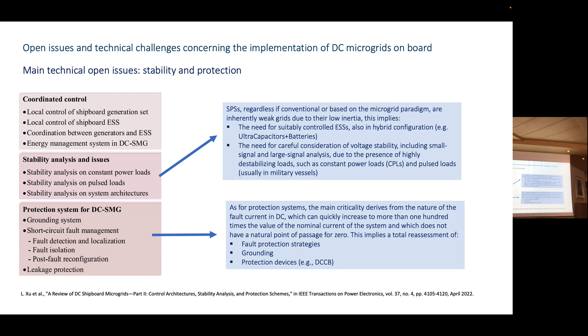So the consolidated protection systems used for AC systems are not appropriate, and the protection system has to be totally revised, starting from fault protection strategies to grounding and protection devices. For this last aspect, some simulations we did show that an electromechanical circuit breaker, for example, is totally unsuitable to clear a fault current in a DC system in time to avoid total outage of the system.